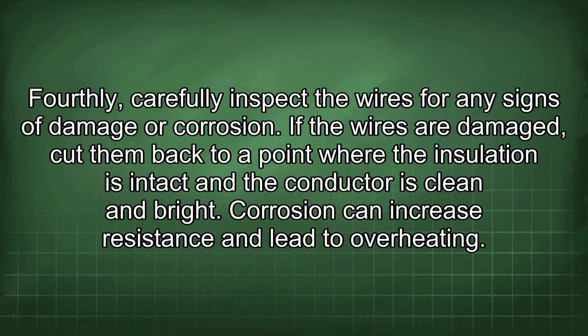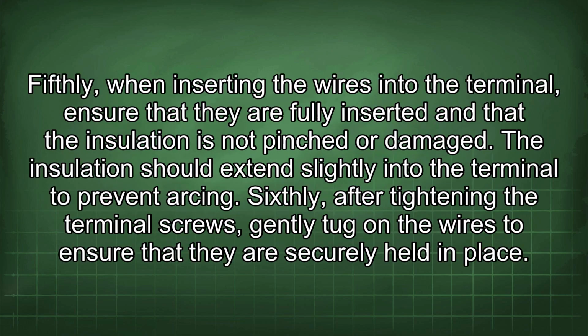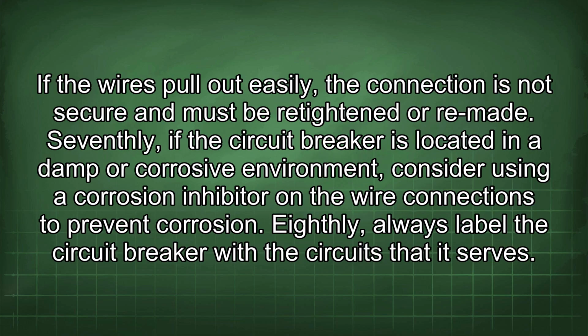Fourthly, carefully inspect the wires for any signs of damage or corrosion. If the wires are damaged, cut them back to a point where the insulation is intact and the conductor is clean and bright. Corrosion can increase resistance and lead to overheating. Fifthly, when inserting the wires into the terminal, ensure that they are fully inserted and that the insulation is not pinched or damaged. The insulation should extend slightly into the terminal to prevent arcing. Sixthly, after tightening the terminal screws, gently tug on the wires to ensure that they are securely held in place. If the wires pull out easily, the connection is not secure and must be retightened or remade.